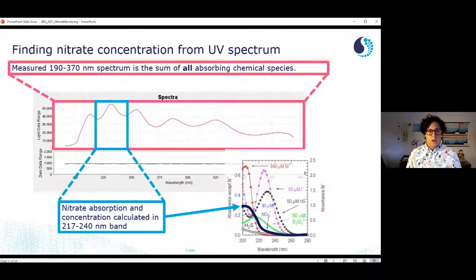Okay. How do you find this nitrate concentration from the UV spectrum? Every time the lamp turns on and every time the spectrometer makes a measurement, it takes a lot of counts. Basically it counts how much light in each of these wavelength bands gets through the seawater and through the nitrate into the spectrophotometer. This is an example of the spectra here, the red line in the middle. The lamp will actually do a wider range, but this is an example of what the spectrophotometer can actually measure.